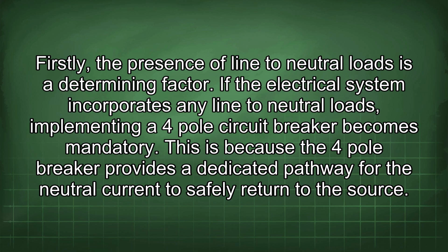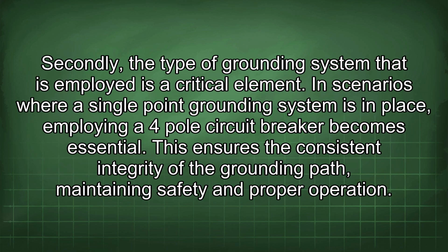This is because the 4-pole breaker provides a dedicated pathway for the neutral current to safely return to the source. Secondly, the type of grounding system that is employed is a critical element. In scenarios where a single-point grounding system is in place, employing a 4-pole circuit breaker becomes essential. This ensures the consistent integrity of the grounding path, maintaining safety and proper operation.